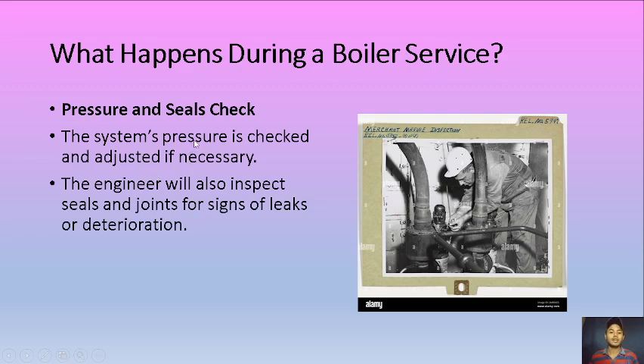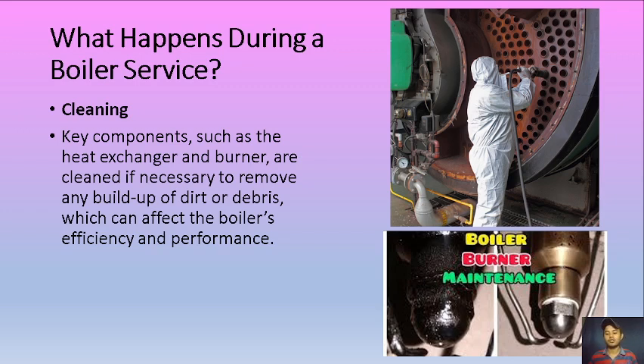Next, for pressure and seals check, the system's pressure is checked and adjusted if necessary. We have pressure gauges all over our boiler, so we can adjust depending on the recommendations of our manufacturer. The engineer will also inspect seals and joints for signs of leaks or deterioration. So before a leakage or damage occurs, you will have a replacement already. Next is cleaning. We have scheduled maintenance for this, but if you suspect that there is a blocked or dirty component, you also have the choice not to wait for the next scheduled maintenance. Key components such as the heat exchanger and burner are cleaned if necessary to remove any buildup of dirt or debris which can affect the boiler's efficiency and performance.